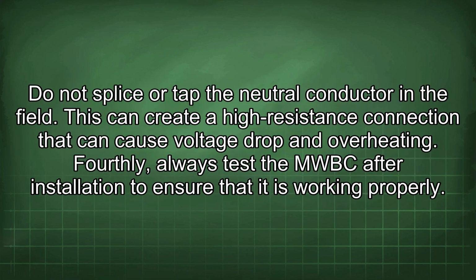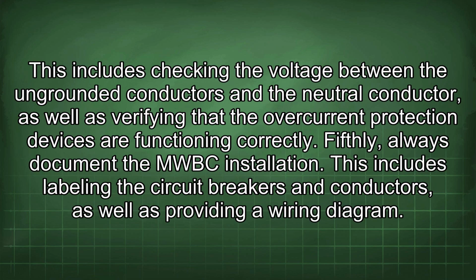Do not splice or tap the neutral conductor in the field. This can create a high resistance connection that can cause voltage drop and overheating. Fourthly, always test the MWBC after installation to ensure that it is working properly. This includes checking the voltage between the ungrounded conductors and the neutral conductor, as well as verifying that the overcurrent protection devices are functioning correctly.